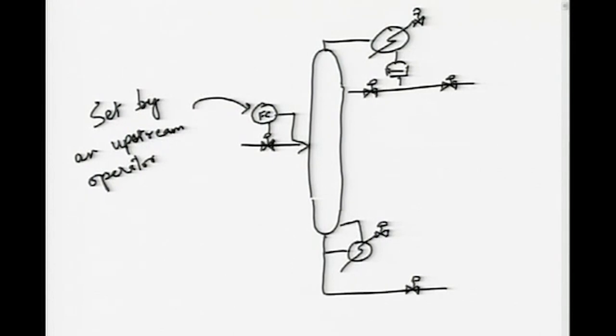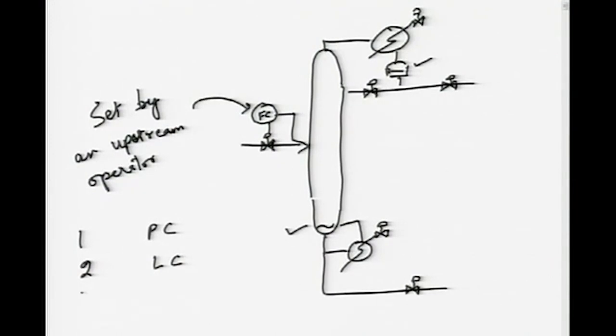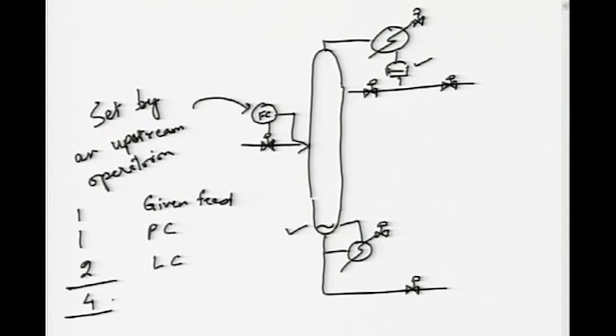So the feed is not in our hands. We have to control two levels — the top level and the bottom sump level. We also have to control the column pressure. Therefore, two valves go for level control, one valve goes for pressure control, and the feed is set from upstream. That leaves us — out of a total of six independent valves, four are taken away. That gives us a degrees of freedom of two.